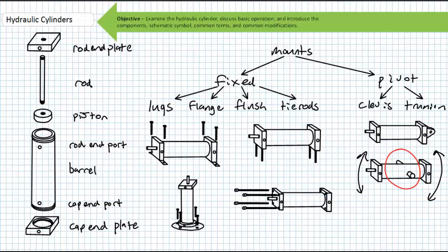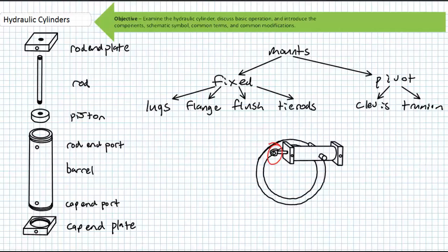These are two common methods of mounting a hydraulic cylinder to hydraulically pitch the blades of a modern wind turbine generator. The rod tip has a clevis mount attached to a slewing bearing, and the barrel is trunnion mounted inside the hub. As the cylinder extends or retracts the slewing bearing and the blade attached to the slewing bearing rolls clockwise or counterclockwise, pitching itself into or out of the wind, thereby changing the angle of attack on our blade and directly controlling the input speed of our generator in the nacelle. This is a great application of hydraulics when pivoting cylinder mounts.